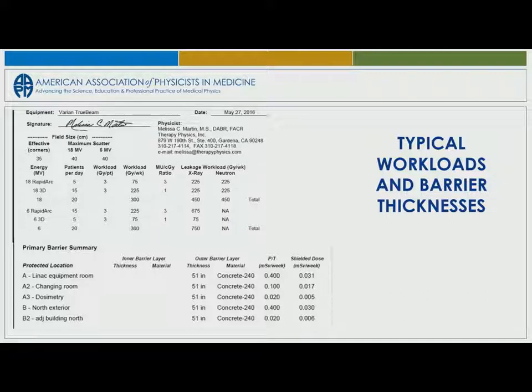So this is how we typically specify the reports. You have your workload specified, and then down at the second part of the page is your primary barrier thickness. And what you want to show in your calculations is what you calculate versus what's permitted. And always you have to have your shielded dose. That shielded dose calculation obviously has to be less than P over T, the permissible limits divided by occupancy. So this column has to be less than that column.